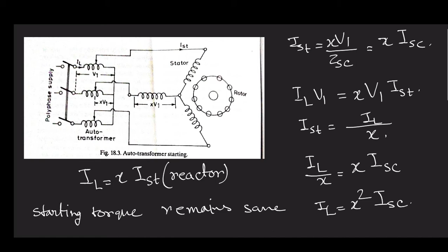So auto transformer starting is beneficial compared to reactor starting, because like reactor, it gives you the same amount of torque, and doesn't offer a torque profile that is poorer than what you could get using a reactor, while it offers a further attenuation of your starting current. That is why in your laboratory, when you perform physical experiments, you will see most of the cases we equip the induction machine with an auto transformer, known as a variac, and we always start our three-phase induction machine using a variac.